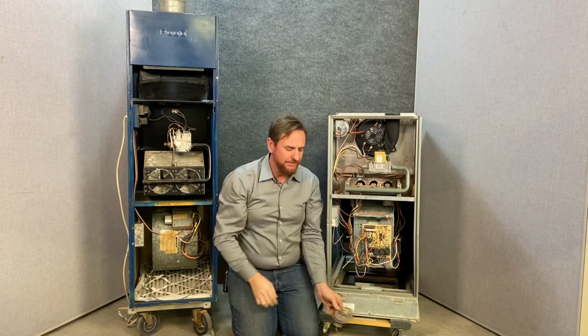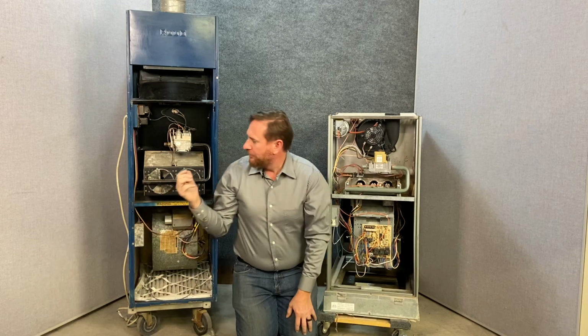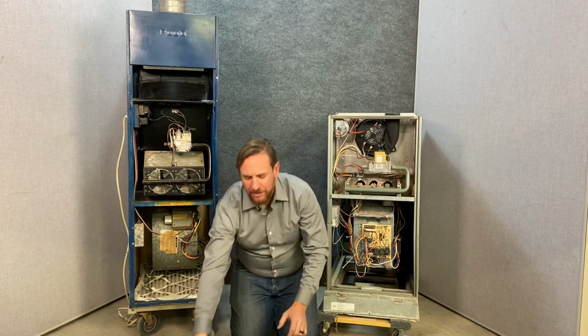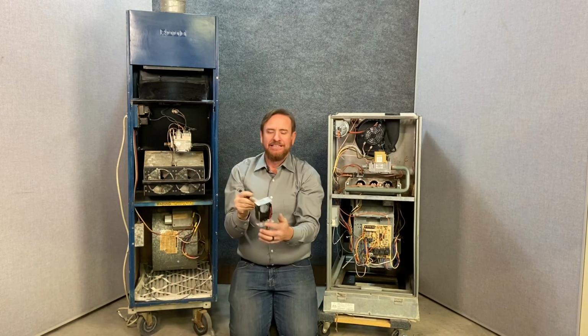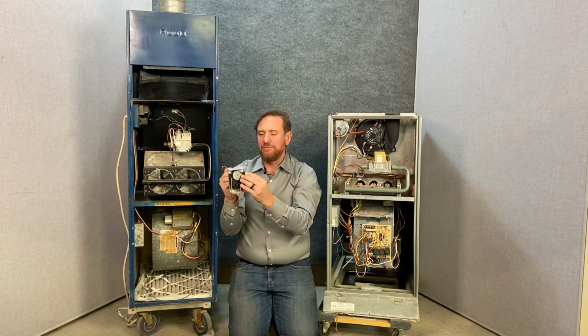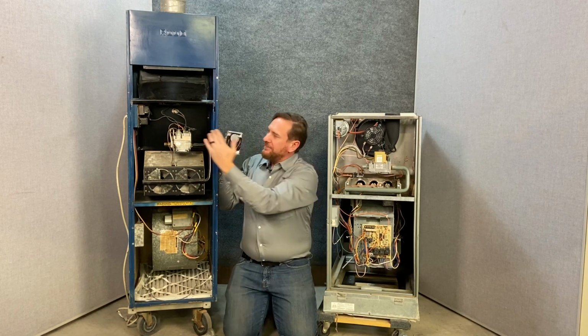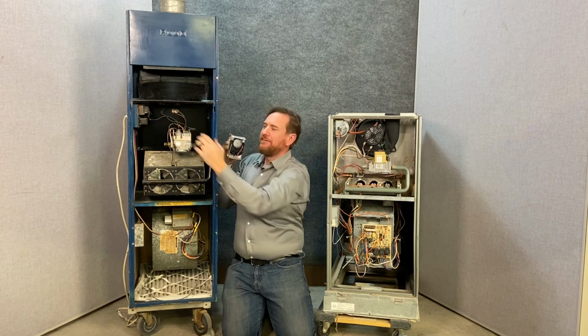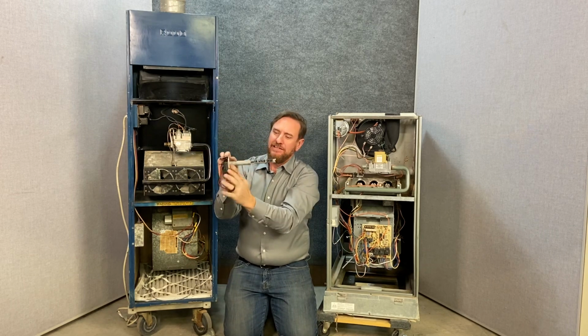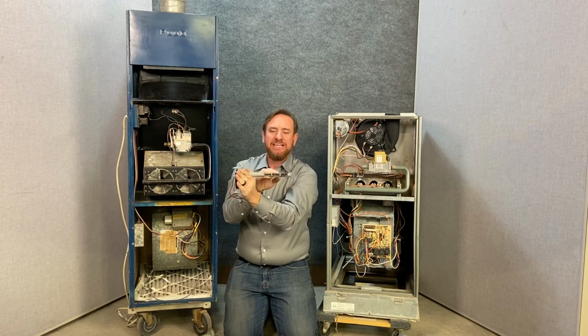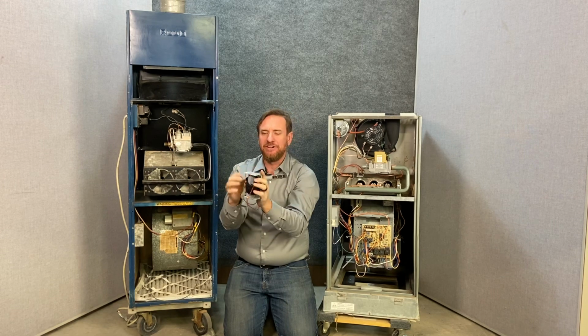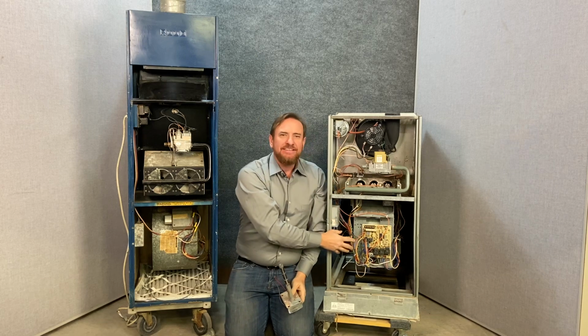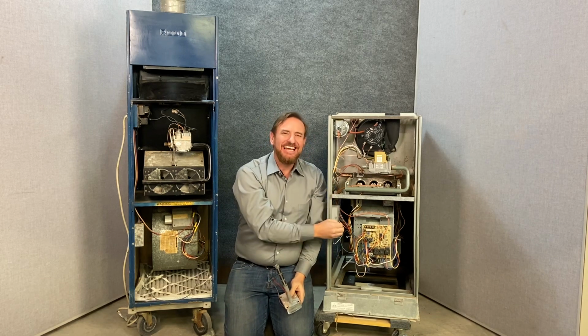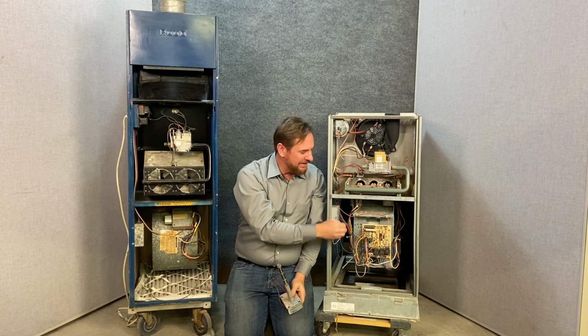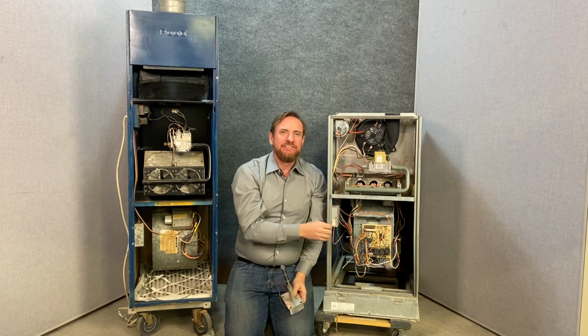Now on this side, what told the blower to come on once it got warm enough was called a fan limit switch. It was a limit switch and a fan switch. So this was all you'd see on this side. It's actually right here. You won't be able to see it at this point, but it would sit between the heat exchangers, and when the heat exchangers got warm enough, the bimetal would turn, and it would bring the fan on. This one uses a preset timer. The engineers have decided exactly how much heat it takes to get heated up to the right point, how long that takes, and it brings the fan on.